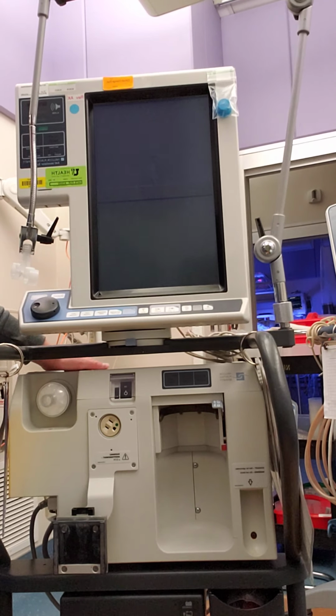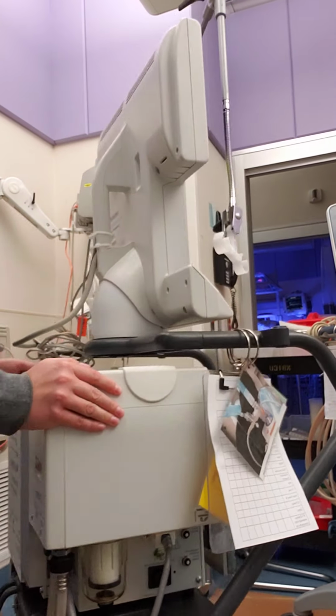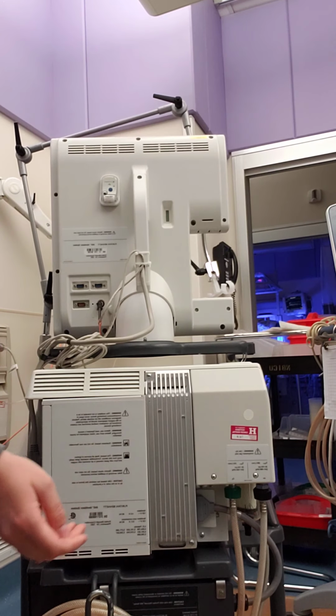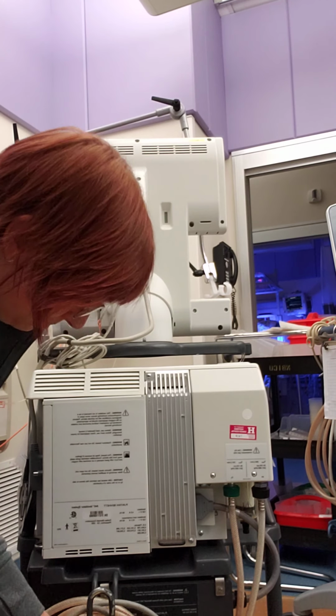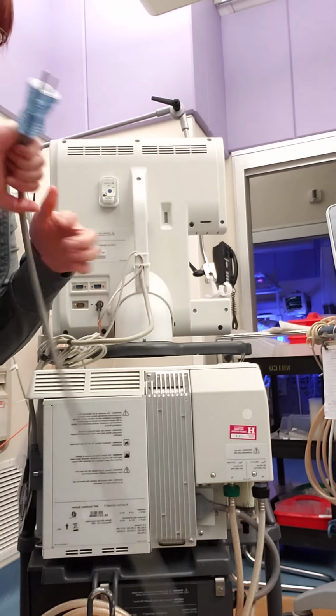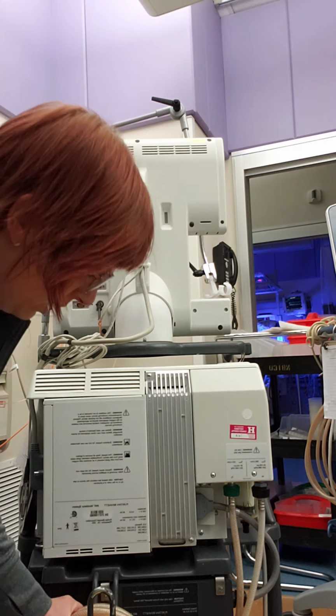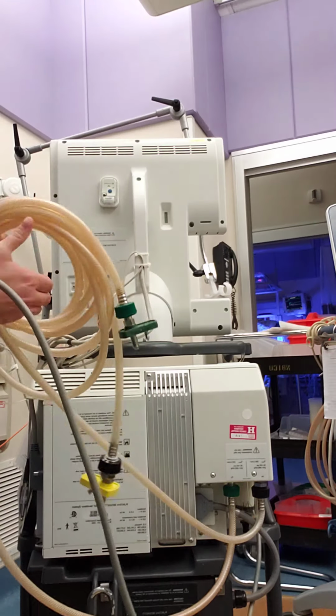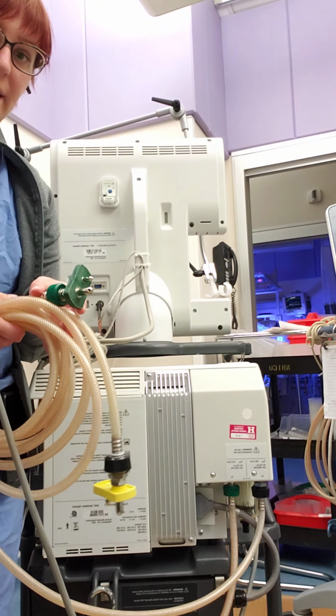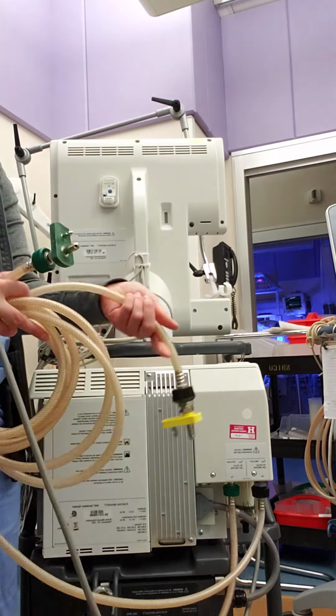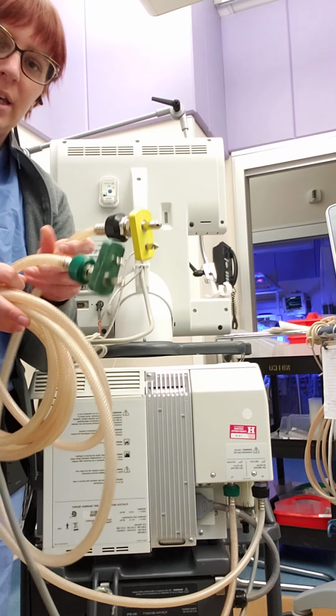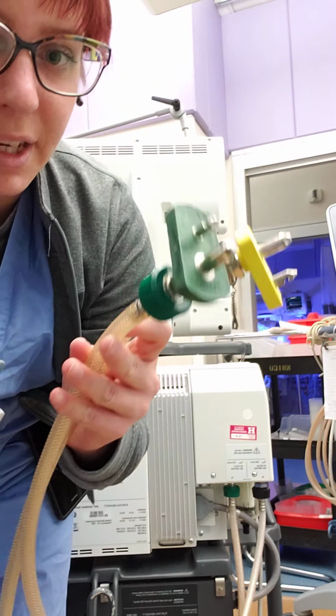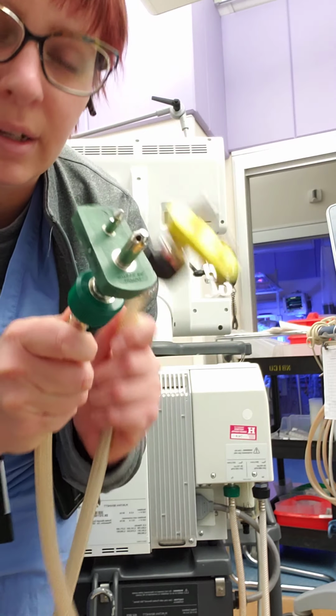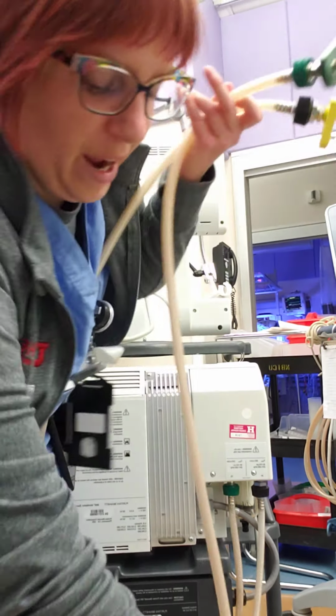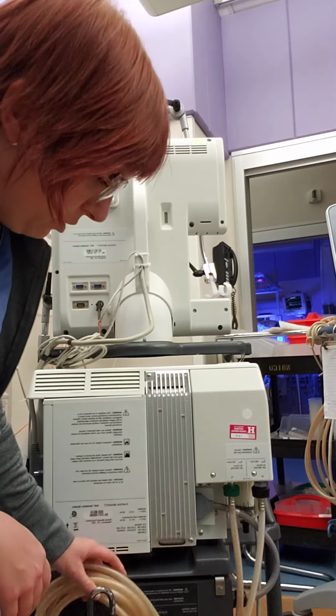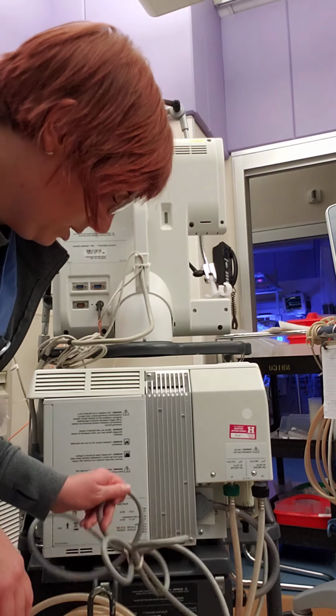If we turn the vent around, just as with any piece of respiratory equipment, we are electrically and pneumatically powered. One thing that makes this a little bit different from the V60 is we have to have both an air and oxygen connection. Remember, oxygen is green, air is yellow. This is so that we can have adequate flow in order to run our ventilator.